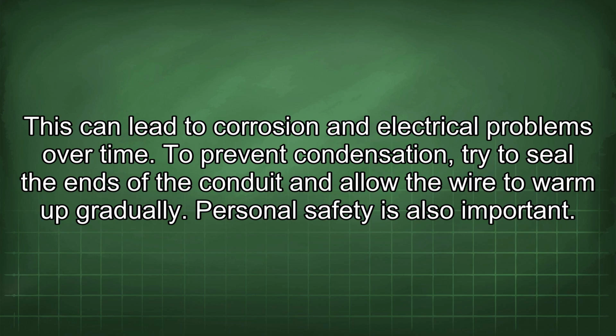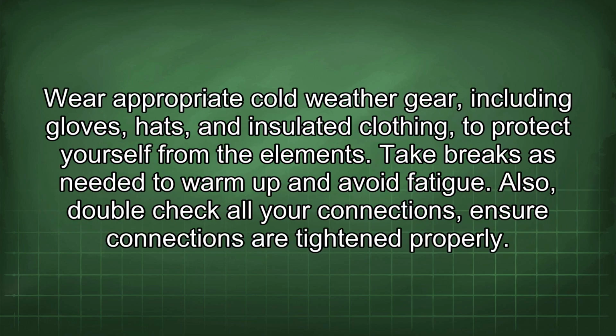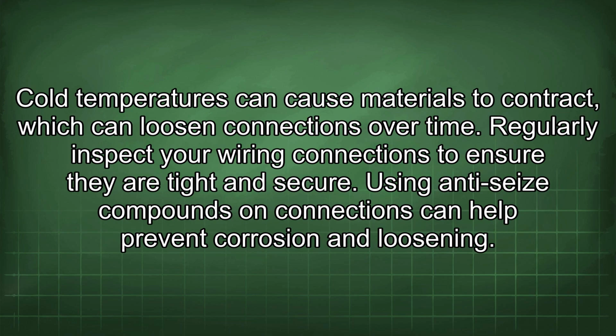Personal safety is also important. Wear appropriate cold weather gear, including gloves, hats, and insulated clothing to protect yourself from the elements. Take breaks as needed to warm up and avoid fatigue. Also, double-check all your connections. Ensure connections are tightened properly. Cold temperatures can cause materials to contract, which can loosen connections over time. Regularly inspect your wiring connections to ensure they are tight and secure. Using anti-seize compounds on connections can help prevent corrosion and loosening.